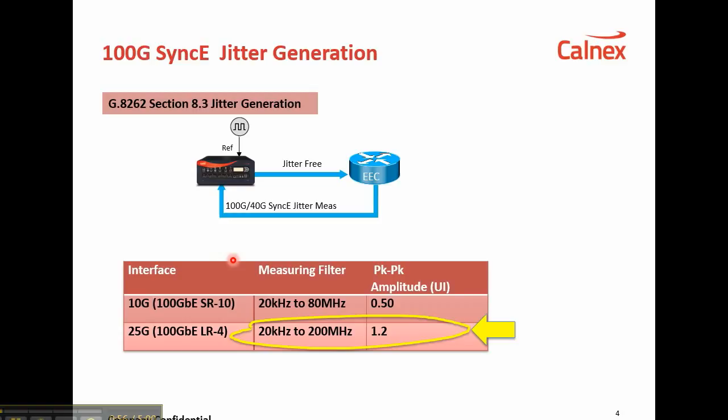The spec that we're measuring to is G.8262, 20kHz to 200MHz, and the limit is 1.2 UI peak-to-peak.